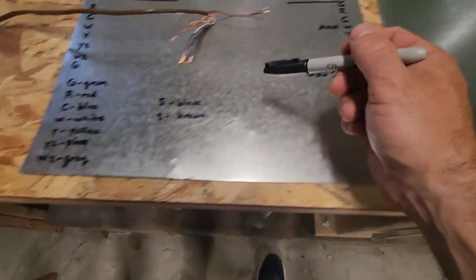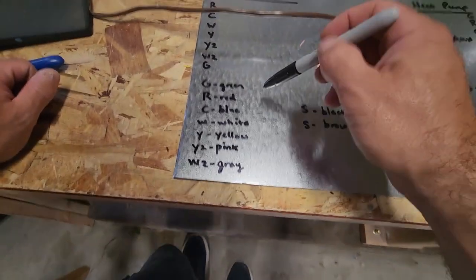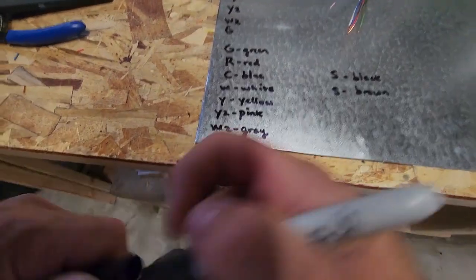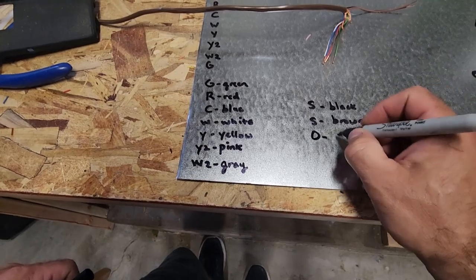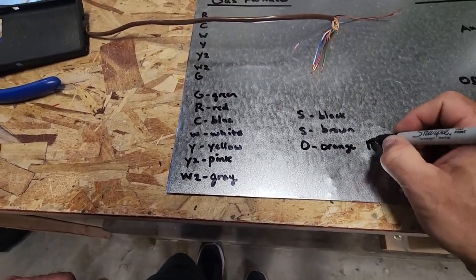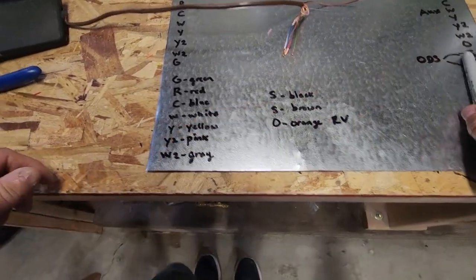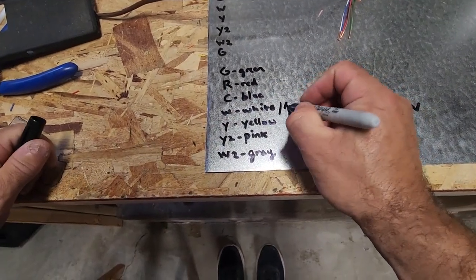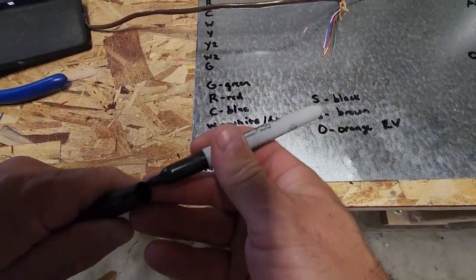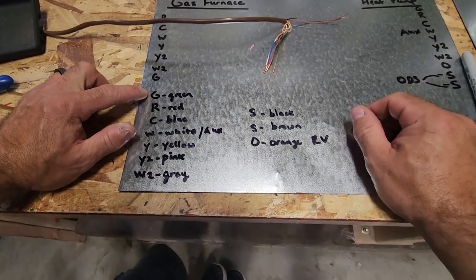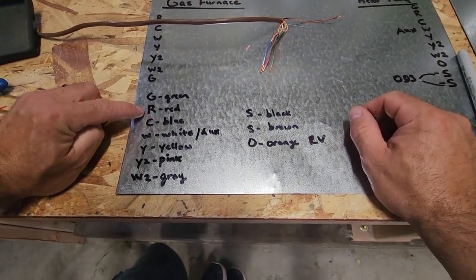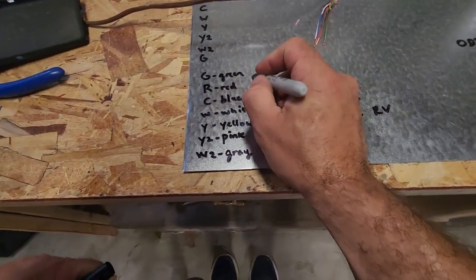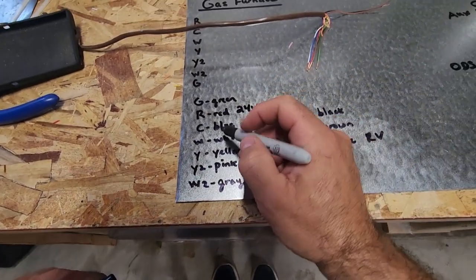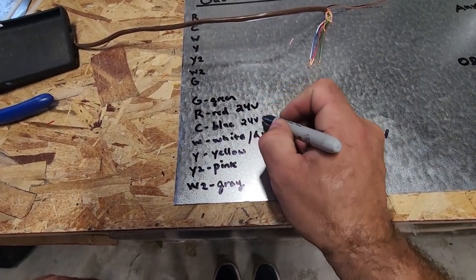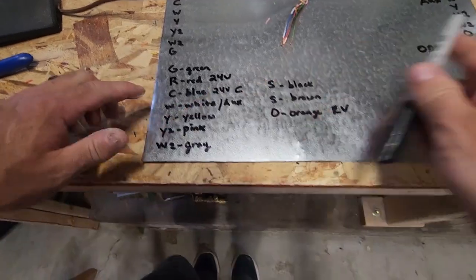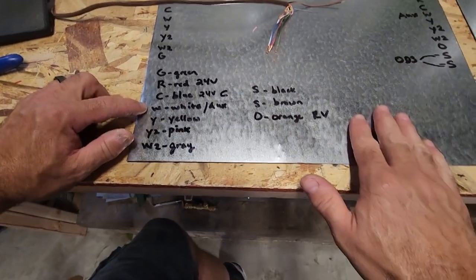So in summary, let's go over here. So G, green, and I didn't write my reversing valve in here. Let's just put it right there. It's going to be orange. And let's just put RV there. And then we can also put, this can be auxiliary for your heat pump. So you have G is always going to be green for your fan. R is always going to be red, 24 volts. C is always going to be blue, 24 volts common. Then we got your white there, auxiliary, W.